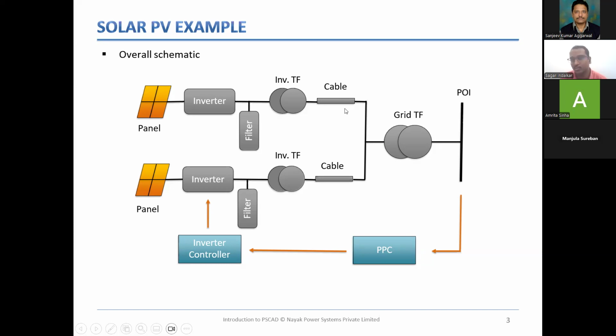And that place will be this. So you may have hundreds of cables and then all bringing it back to one location. Of course, this cable will have its own reactance, reactive power absorption. But the voltage here is still 33 kV, not up to what the grid is requiring. So you have something called the main power transformer, which steps up this voltage from 33 kV to your POI voltage. The point of interconnection, POI, is the place where your entire plant output will be connected. It's the location at the grid where the entire output of the plant is delivered. So these terms are very important because as we go ahead, I'm going to use these terms quite a lot.